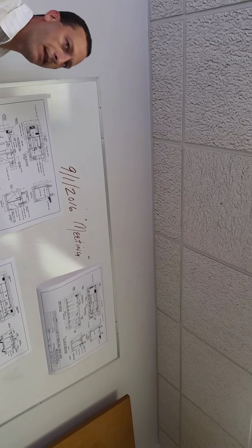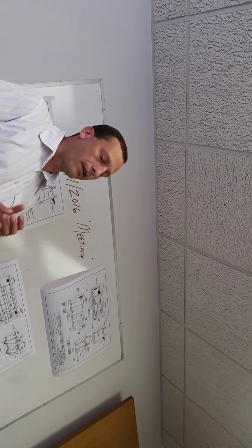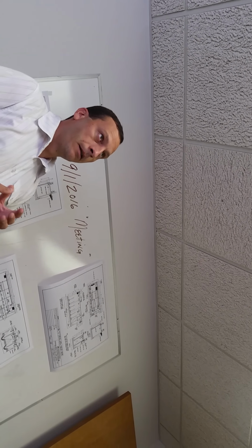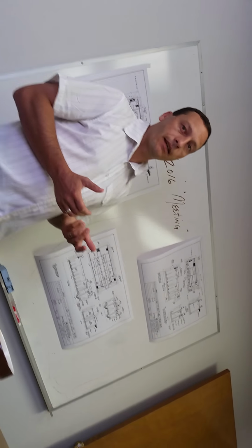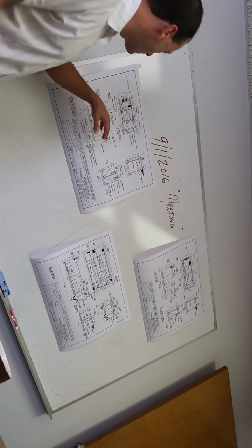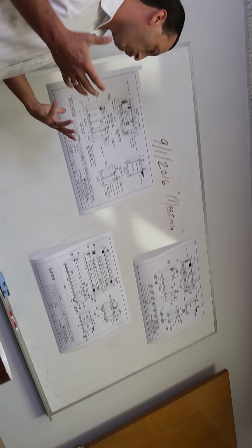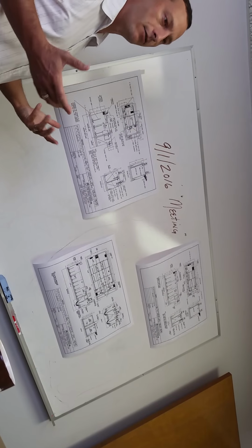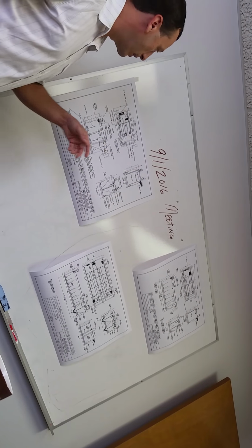Most of this is based on retention time. Like Paul said, with Ten State Standards, there are specific clarifier volumes that we're trying to hit, and there are specific surface settling rates. The surface settling rate is a specific requirement according to Ten State Standards. It has to be within a certain number of gallons per day per square foot.